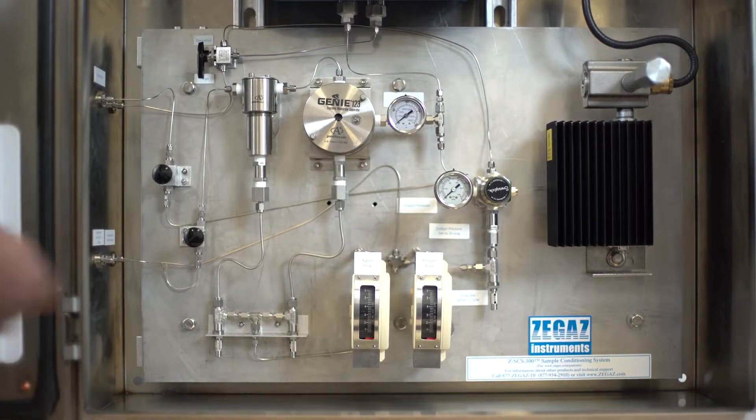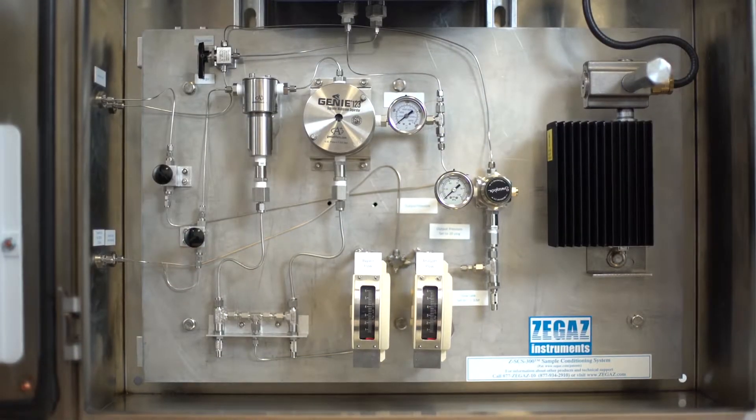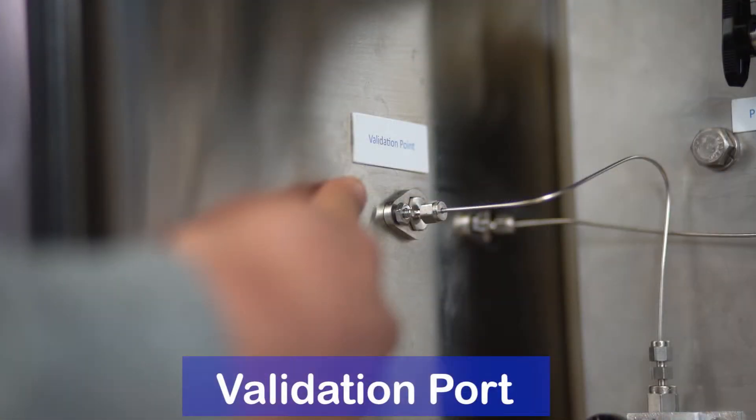The high pressure bypass for each of the filters is combined with the sample output and also reduced in flow and vented to a safe area. There is a validation port to introduce a known gas to the analyzer to validate the function of the analyzer.